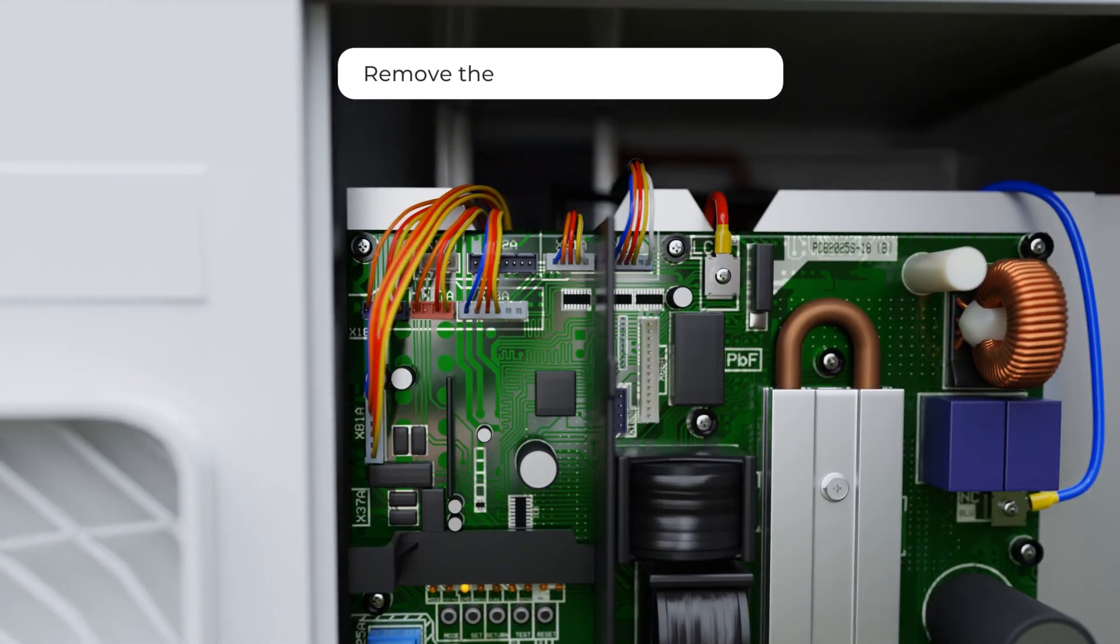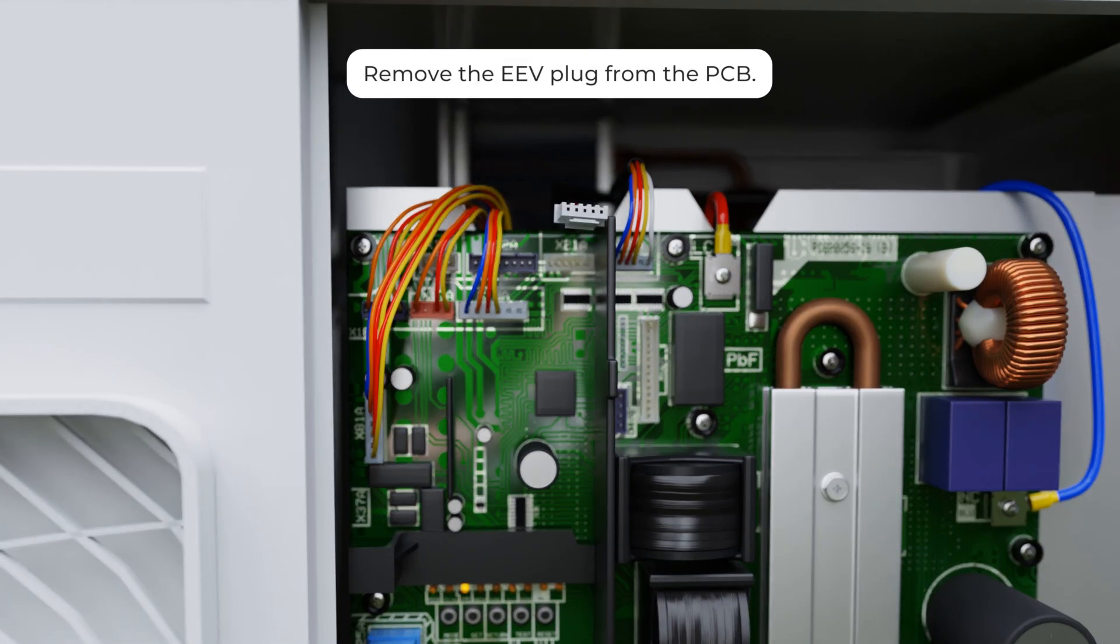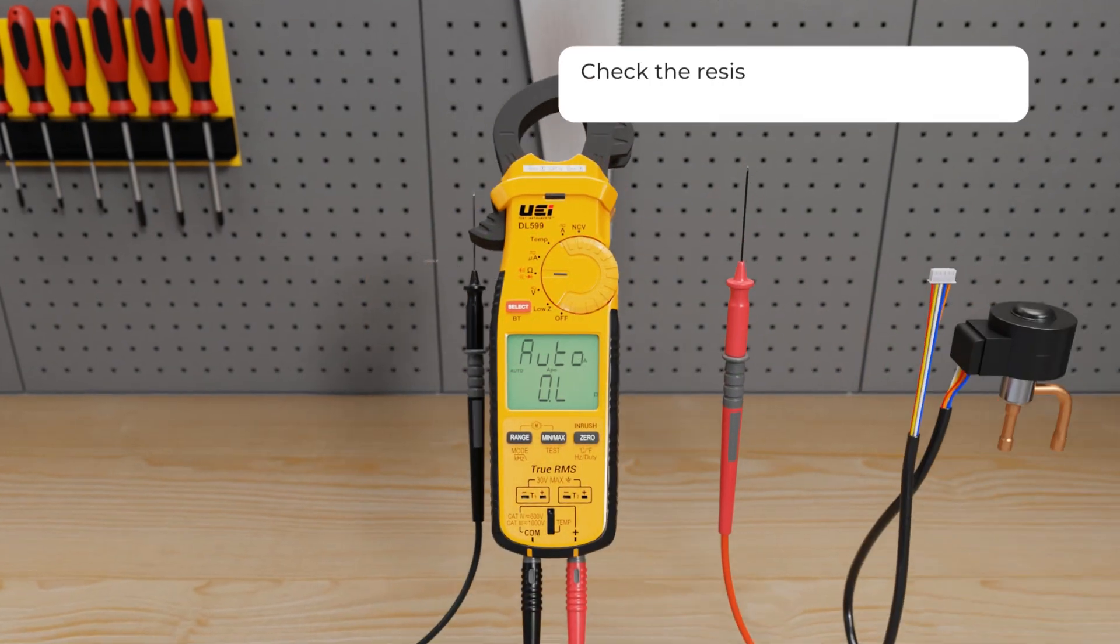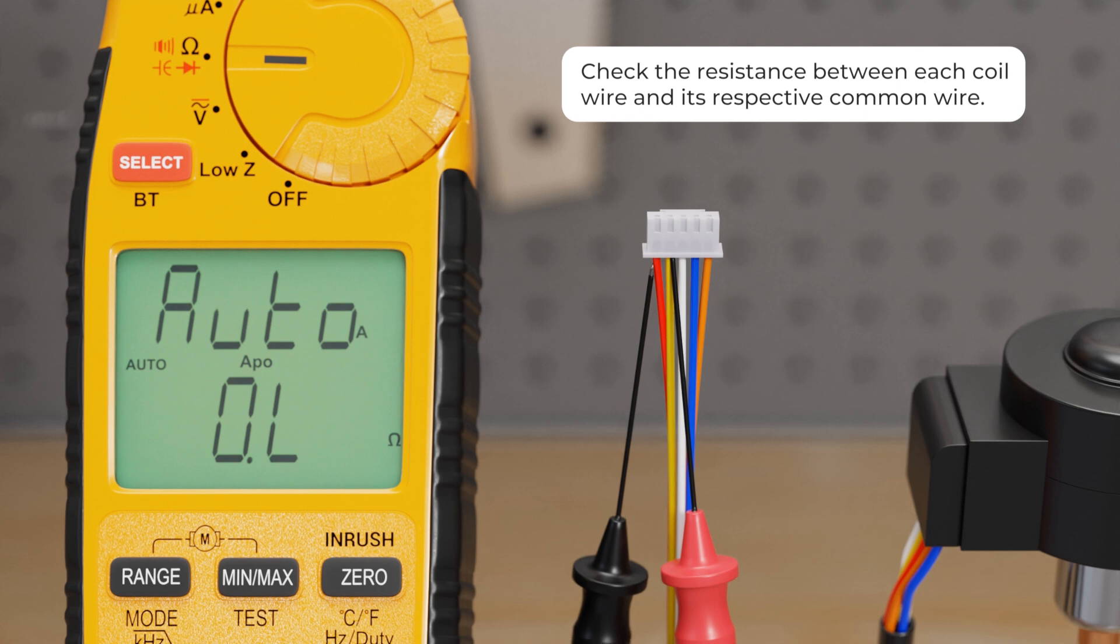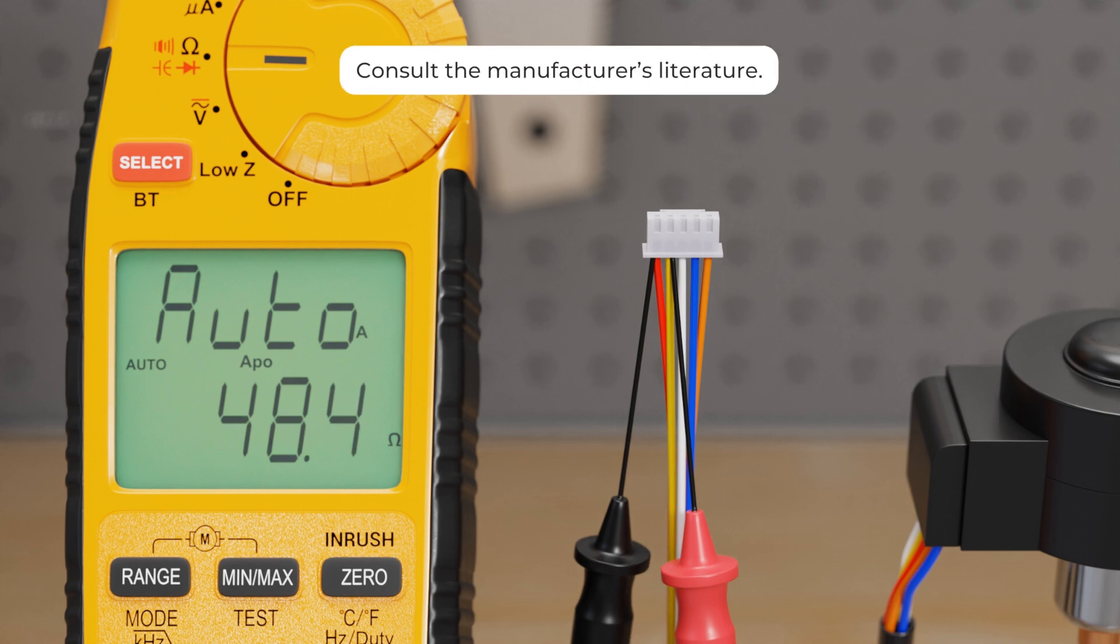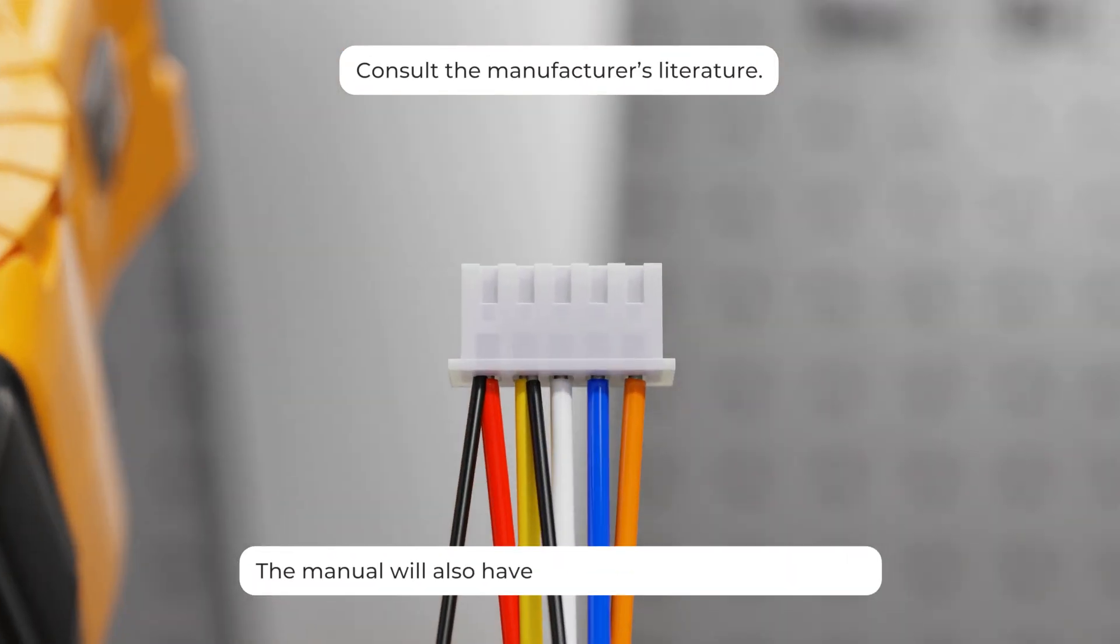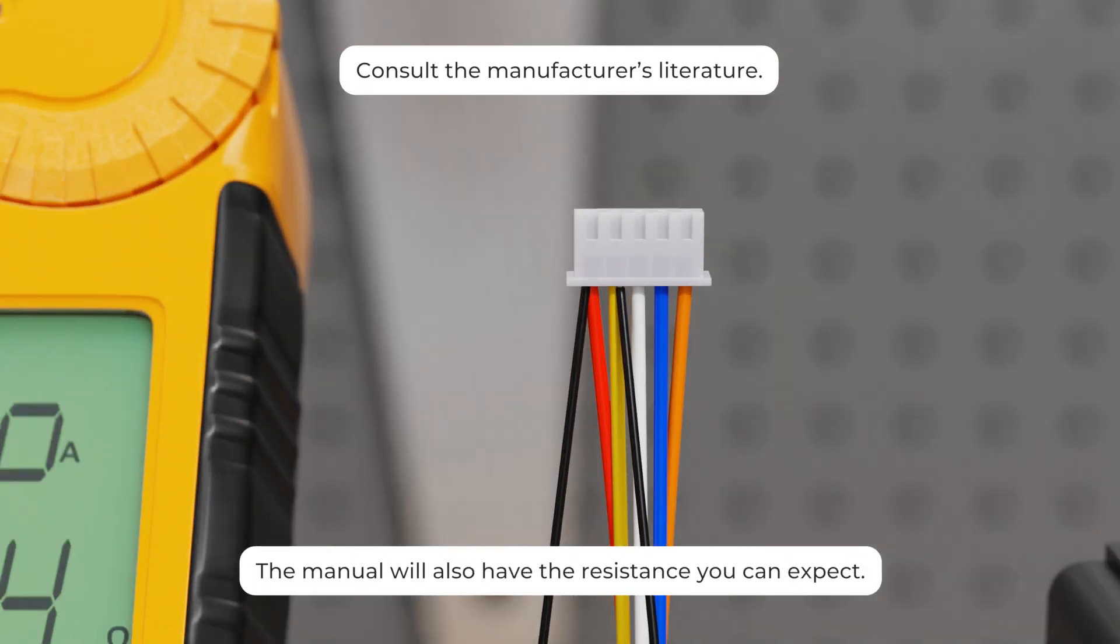Then remove the EEV plug from the PCB. Check the resistance between each coil wire and its respective common wire. If you don't know which wires are which, consult the manufacturer's literature. The manual will also have the resistance you can expect.